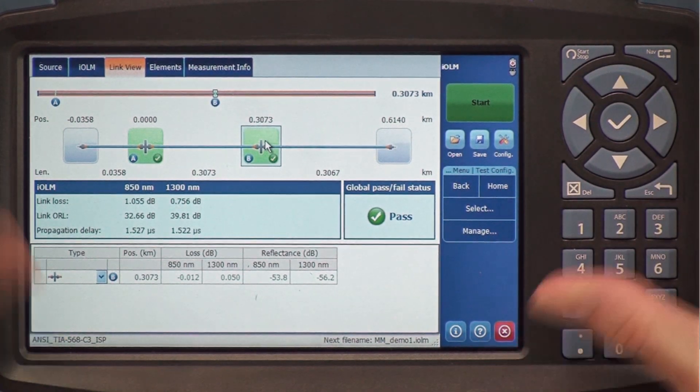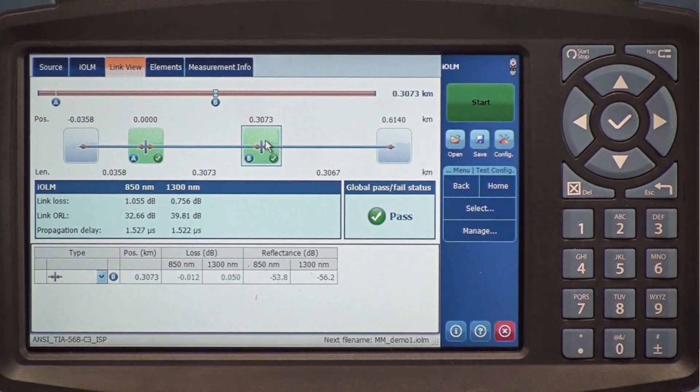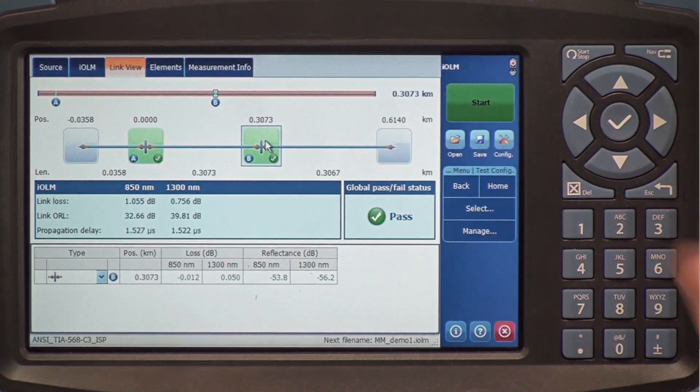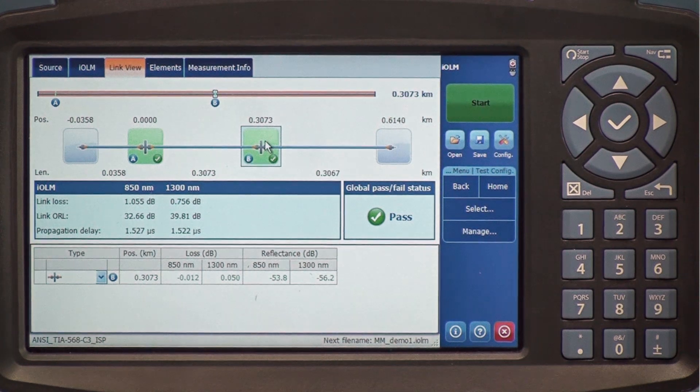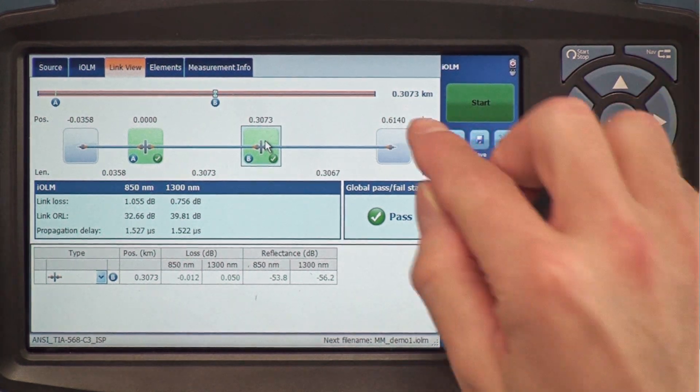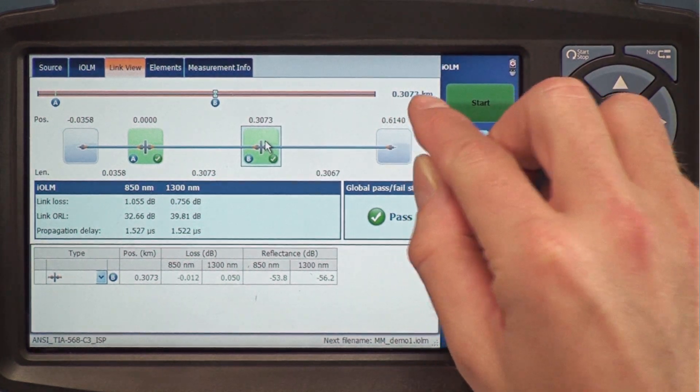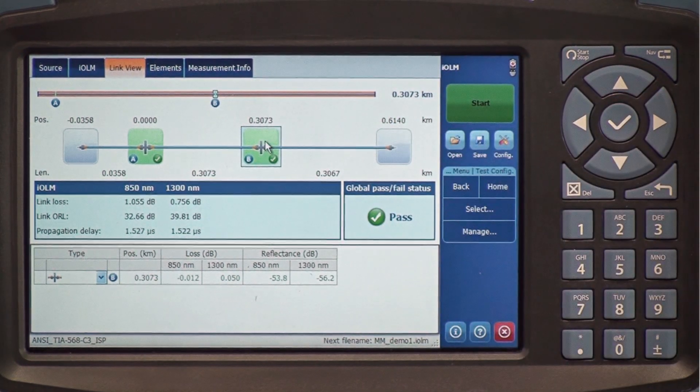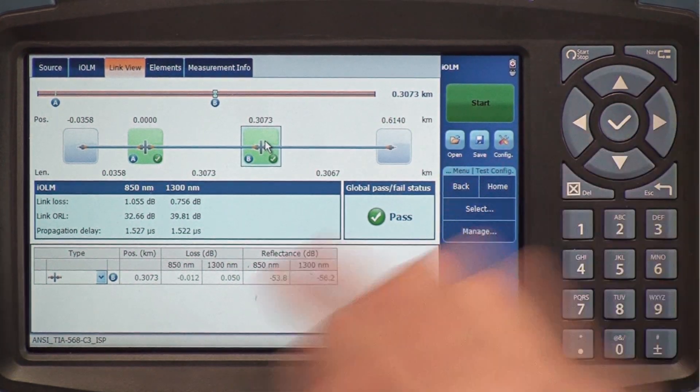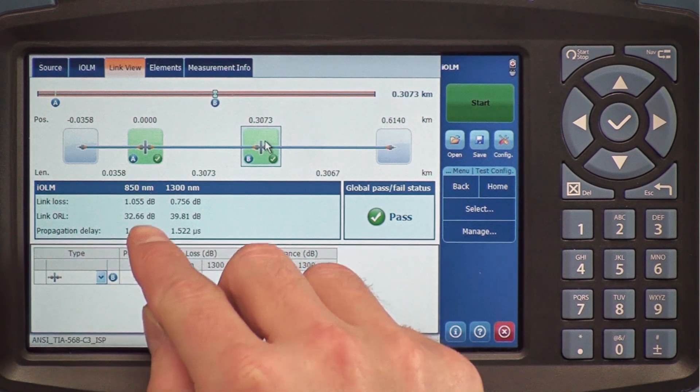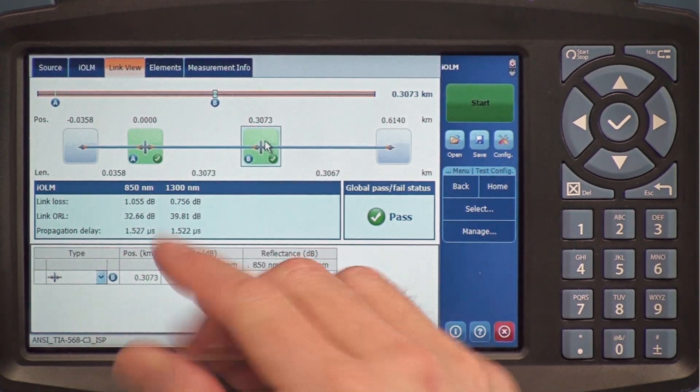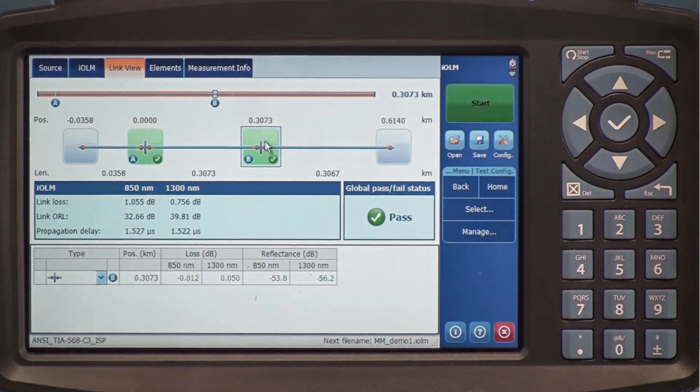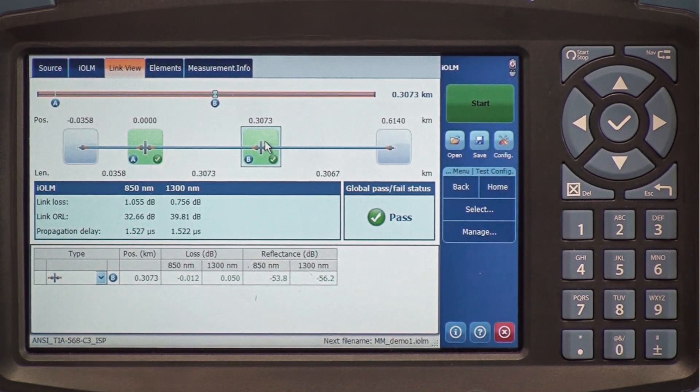In this same page, we get all the information we need to properly certify the cable. On top here, we have the total length of the fiber, the total link loss, and the total link ORL for both wavelengths 850 and 1300.